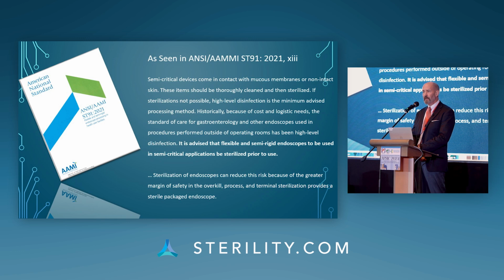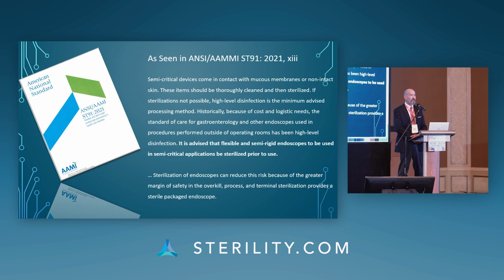The conclusion in this AAMI guidance document, which, by the way, I would encourage all of you who are involved in endoscope reprocessing to purchase, has a wealth of information in it. The conclusion in this document is that it is advised that flexible and semi-rigid endoscopes to be used in semi-critical applications be sterilized prior to use. That right there is the reclassification of Spaulding. Semi-critical devices, endoscopes, should be sterilized.